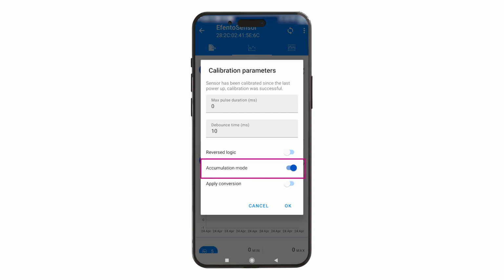Accumulation mode. The pulse counter can operate in one of 2 modes. Enabled: the counter counts all pulses from the moment the device is turned on and the initial calibration point is set. Once the maximum value is reached, the device will restart counting from 0. This mode is enabled by default. Disabled: the counter resets its value after each measurement period.